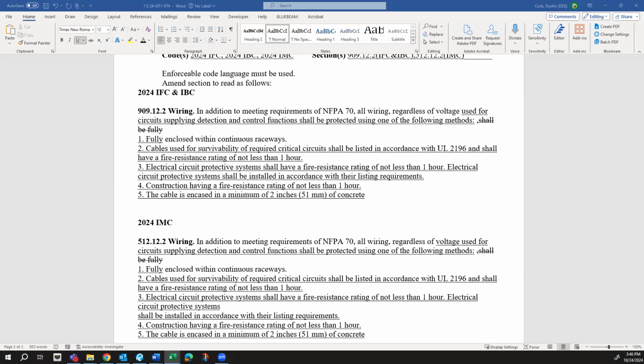Right, and we definitely agree with the concern from an enforcement point of view, and we run into the same issue as well. We're doing a lot of smoke control design. When we get to this, we definitely look into the continuous raceway requirements as part of reviewing the fire alarm drawings. And then technically, this is under the 909 section, so the smoke control special inspector should, I would say, review these conditions or requirements to be applied properly. But I agree, not everything is inspected and properly verified in the field.